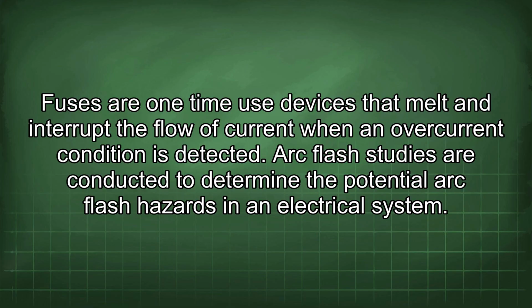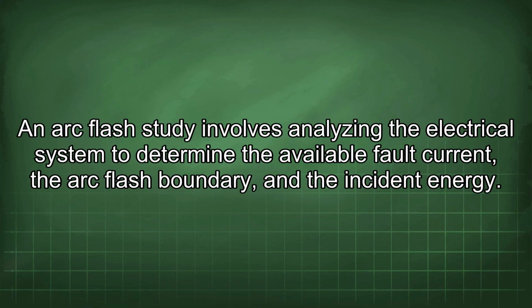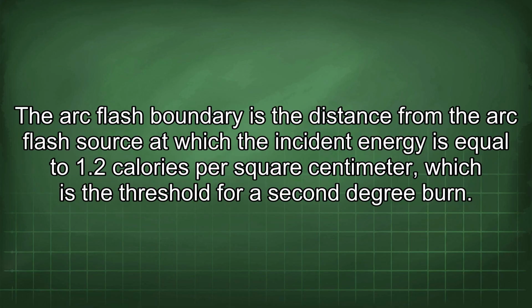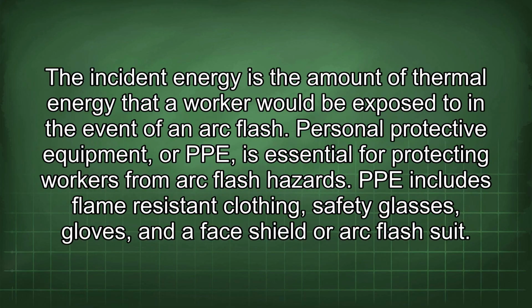Arc flash studies are conducted to determine the potential arc flash hazards in an electrical system. An arc flash study involves analyzing the electrical system to determine the available fault current, the arc flash boundary, and the incident energy. The arc flash boundary is the distance from the arc flash source at which the incident energy is equal to 1.2 calories per square centimeter, which is the threshold for a second-degree burn. The incident energy is the amount of thermal energy that a worker would be exposed to in the event of an arc flash.